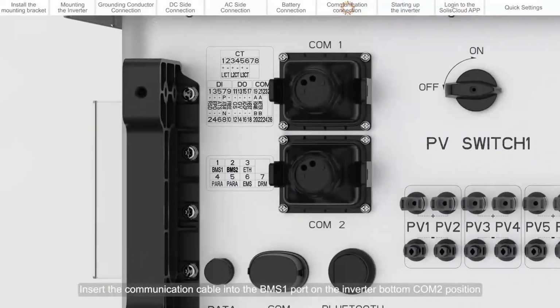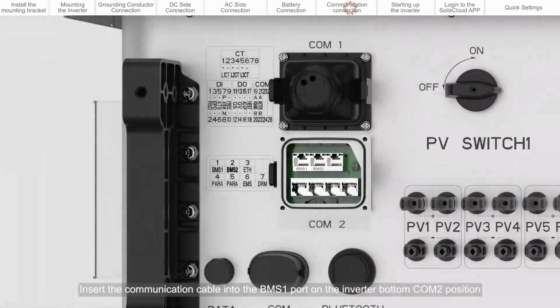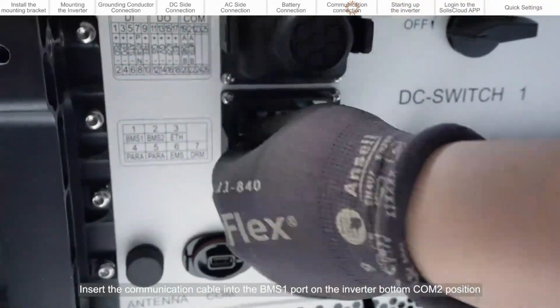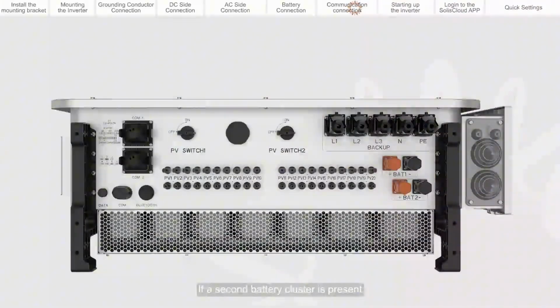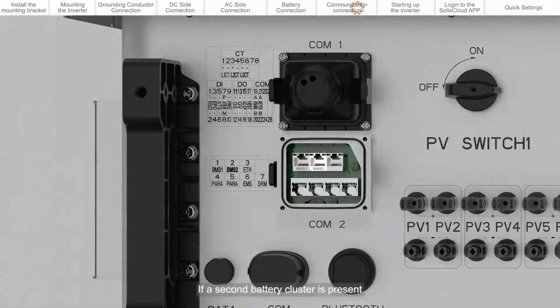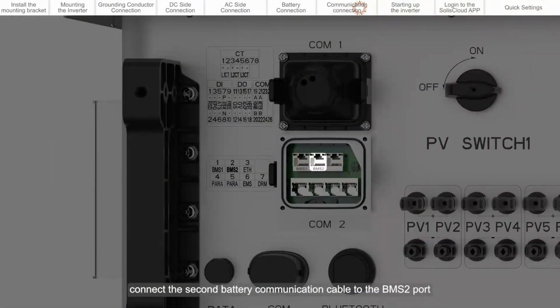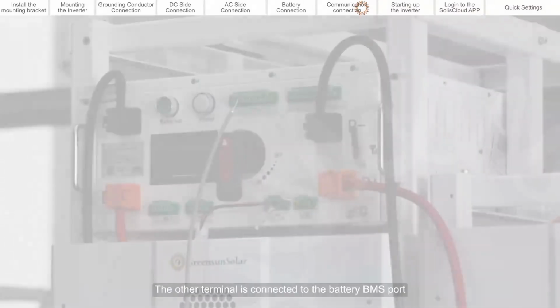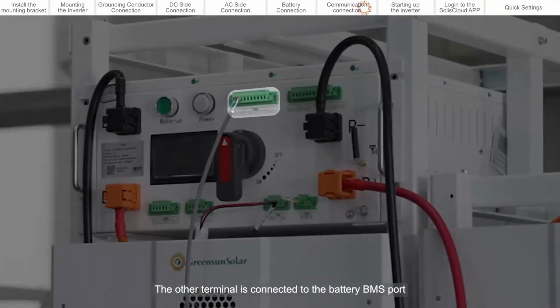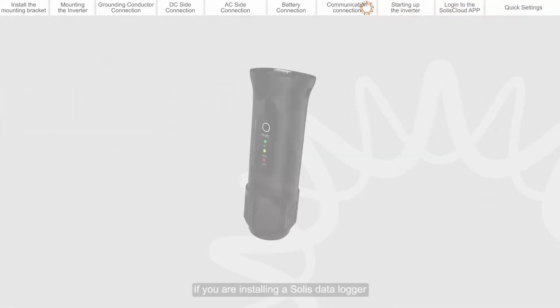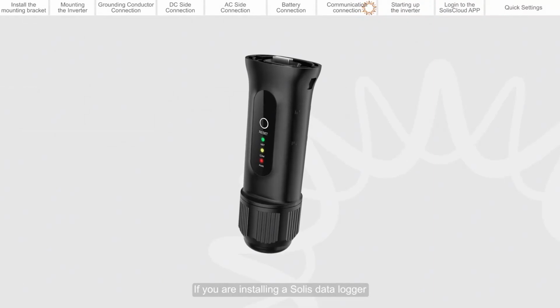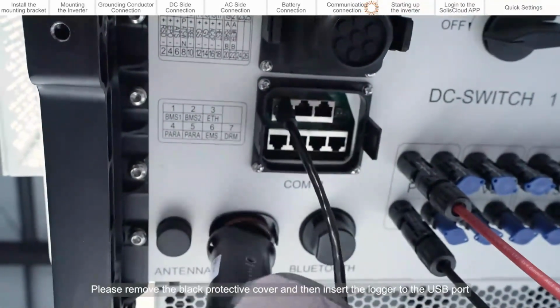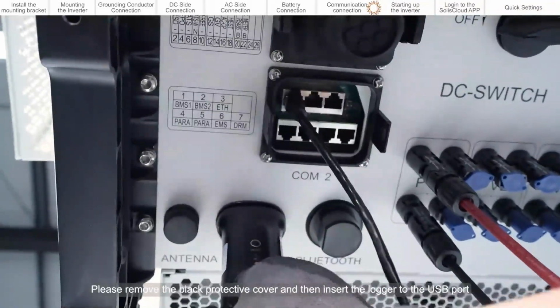Insert the communication cable into the BMS1 port on the inverter bottom COM2 position. If a second battery cluster is present, connect the second battery communication cable to the BMS2 port. The other terminal is connected to the battery BMS port. If you are installing a Solis data logger, please remove the black protective cover and then insert the logger into the USB port.